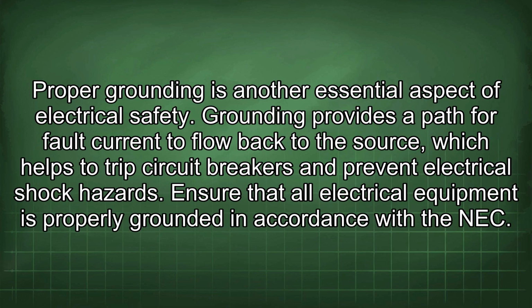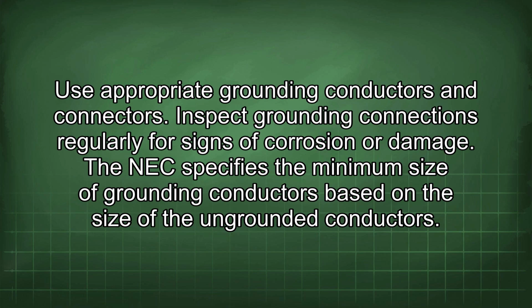Proper grounding is another essential aspect of electrical safety. Grounding provides a path for fault current to flow back to the source, which helps to trip circuit breakers and prevent electrical shock hazards. Ensure that all electrical equipment is properly grounded in accordance with the NEC. Use appropriate grounding conductors and connectors. Inspect grounding connections regularly for signs of corrosion or damage.